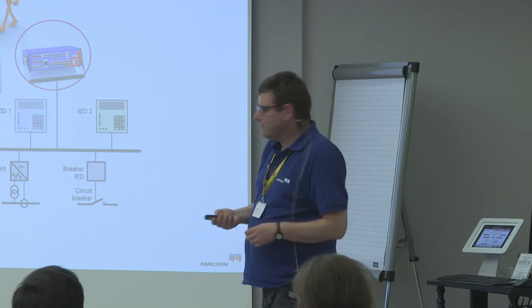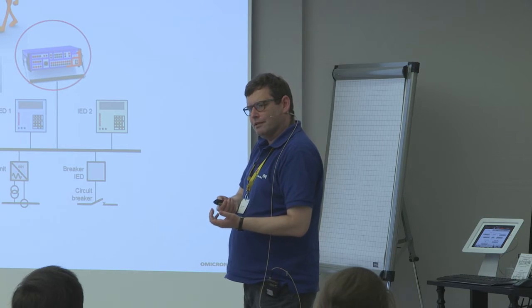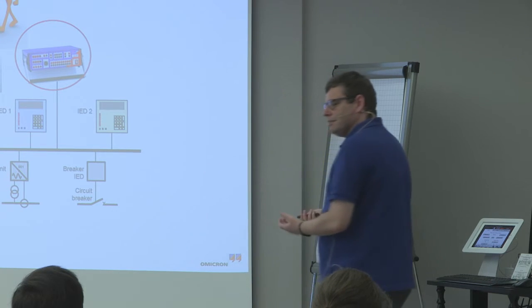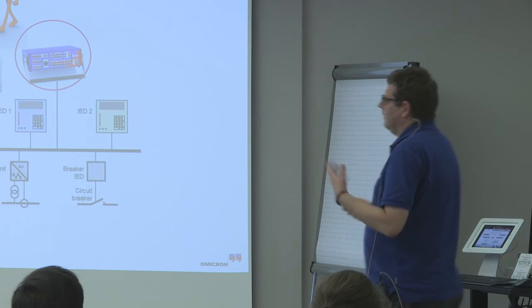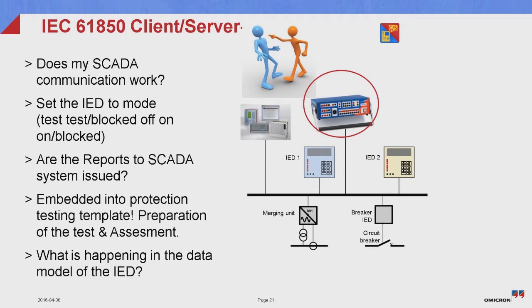This sounds a little bit complicated, but it also allows me to test the SCADA communication. And another main advantage is that I can embed this into the conventional protection testing. And this makes it much easier than if you just do this with any additional software. And another very important topic is that you can check the data model of the IED during the protection testing.